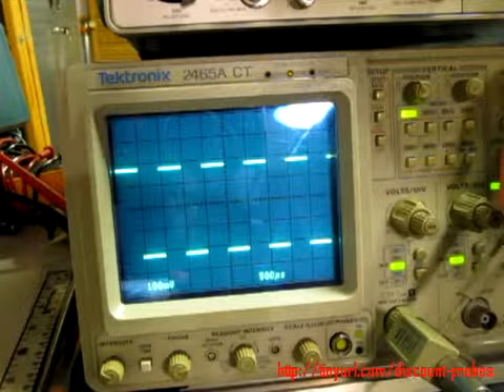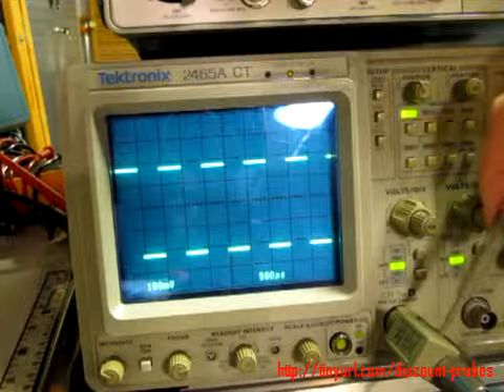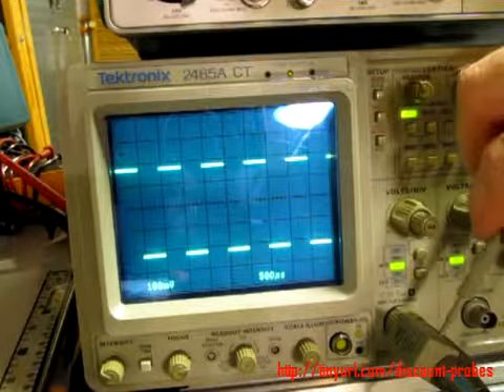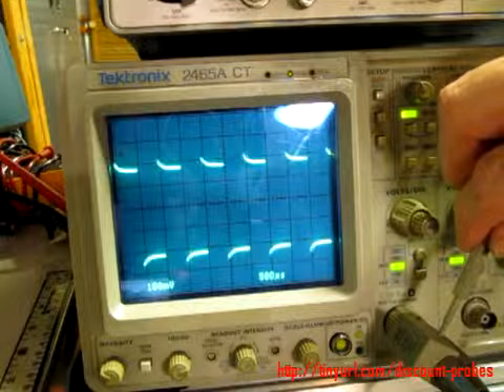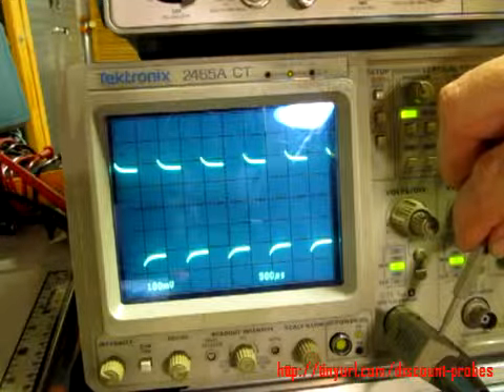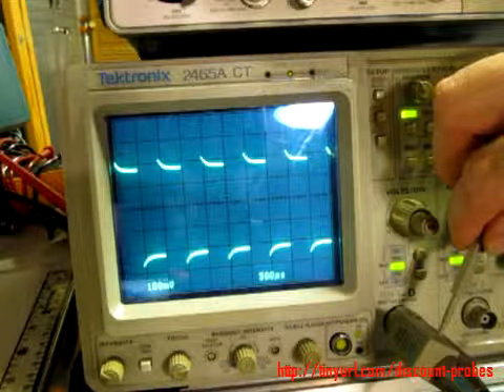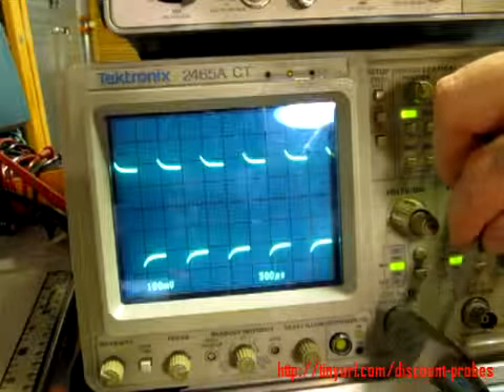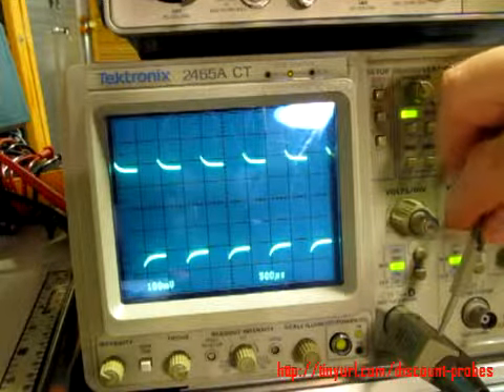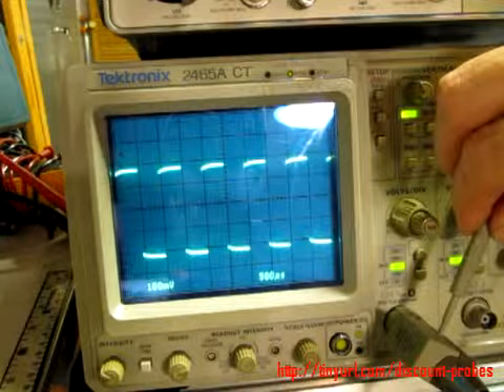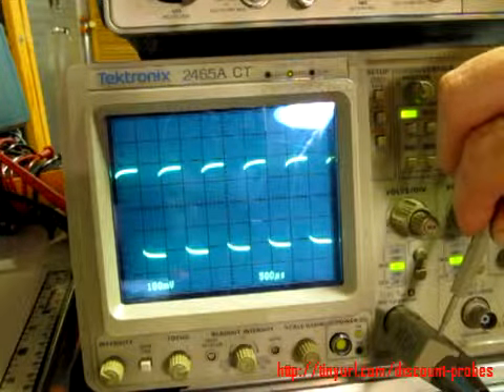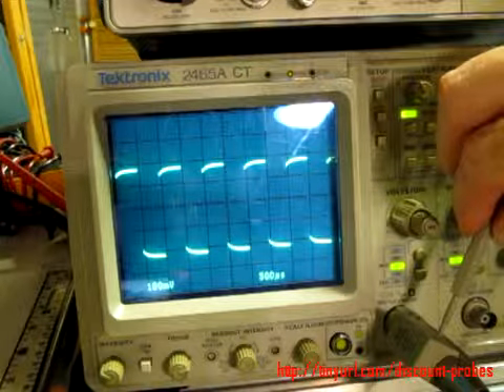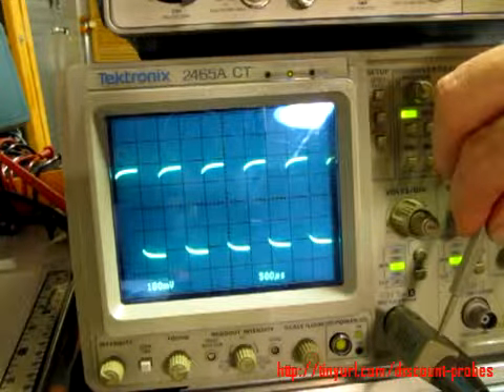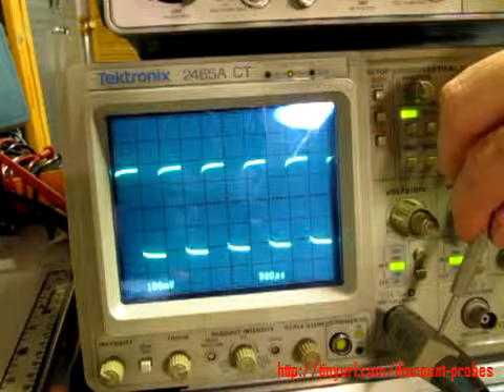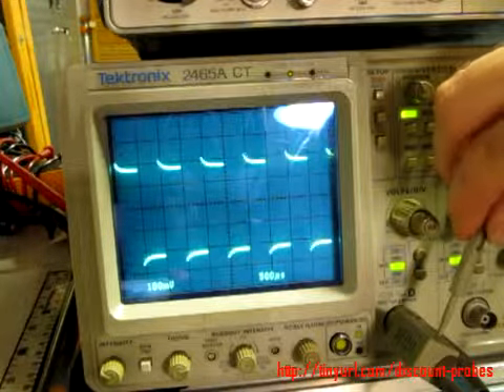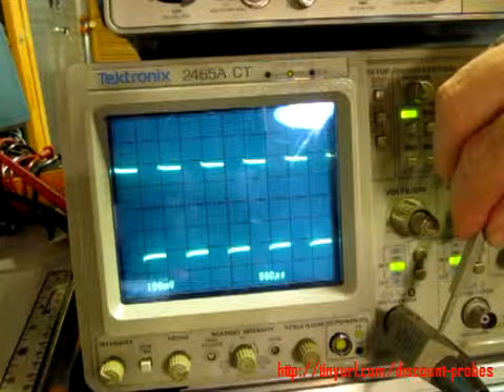And here's what it looks like if you have it misadjusted. Let's see if I can engage the screwdriver in here. There we go. And you can see if I make that capacitor too big, we're going to couple more high frequency energy in, and we're going to get this overshoot on the rising and falling edges of the square wave. And if we adjust it the other way, where that capacitor is too small, now we're low pass filtering that square wave, and we get this kind of rolled off response there. So the idea is to adjust this thing. If we go back and forth, we can adjust that until we get a really nice looking square wave.